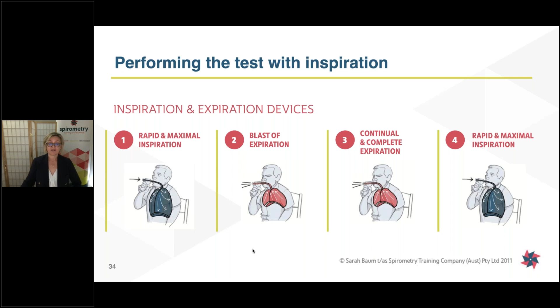As we know it, spirometry has just been expiration typically in primary care. However, what will change is that you'll start the test on the machine, taking that full breath in, blowing out as fast as we can, continually and completely. And then right at the end, when we are at the end of exhalation, we would take a rapid and maximal breath in at the end before we come off that mouthpiece. So that's what you'll see. If you can add an FIVC in your measurements, it's a great thing to do.